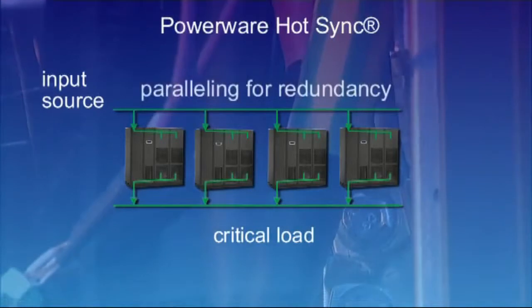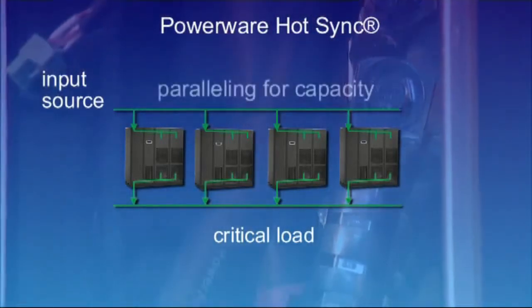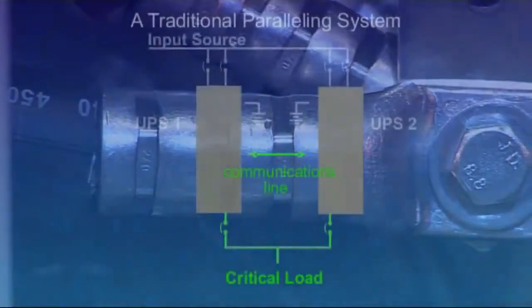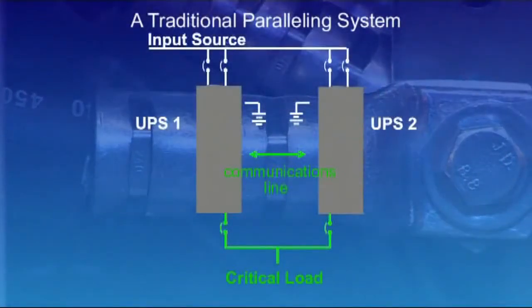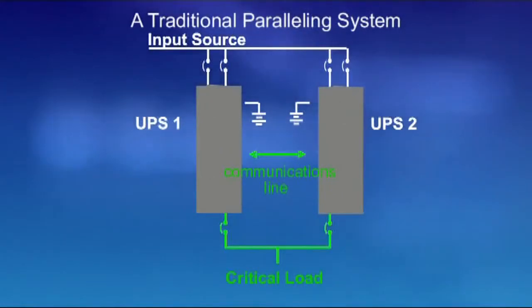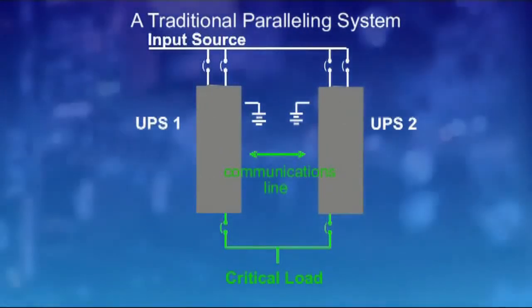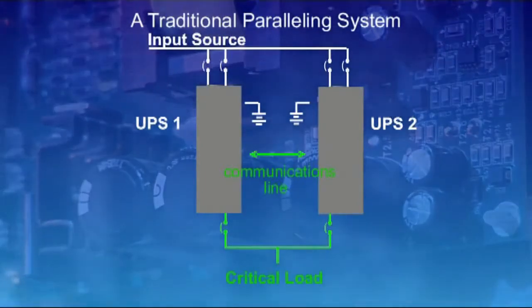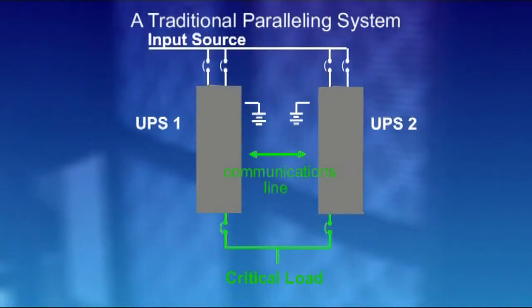Paralleling can be used to gain redundancy between UPS modules and to add capacity to the system. A traditional parallel UPS system depends on an output synchronization signal being transmitted between the parallel connected UPS modules via a communications line. Even in the most advanced systems, an external sync signal is required in order to ensure a balanced load share.